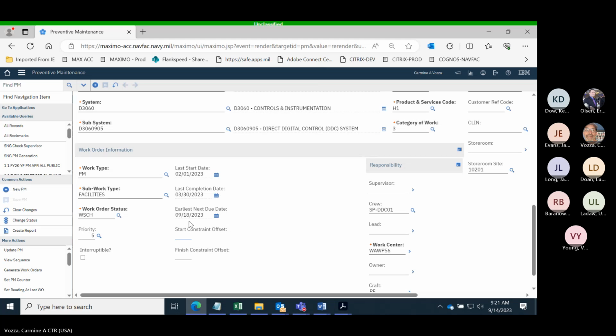So every night it just goes out those number of days. So if AutoGen ran last night, tonight it's only going out 14 days again. 13 of those days is already done. So really, it's only picking up PMs at the end, or PMs that were fixed and moved into that window. All right. So we're going to generate this one now.